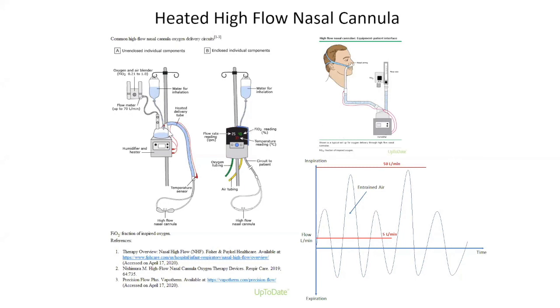And that's a really key point to this modality. In terms of the setup, briefly, the parameters that you want to set up are 2 things. It's the flow rate, and then it's the oxygen concentration. Often for adults, you may start with a flow rate ranging between 20 to 35 liters per minute. And then typically most people managing high flow nasal cannula will try to optimize the flow first and then work on the oxygen piece second. And the idea is you want to try and minimize your oxygen use. So max out your flow and then blend in the oxygen as needed.